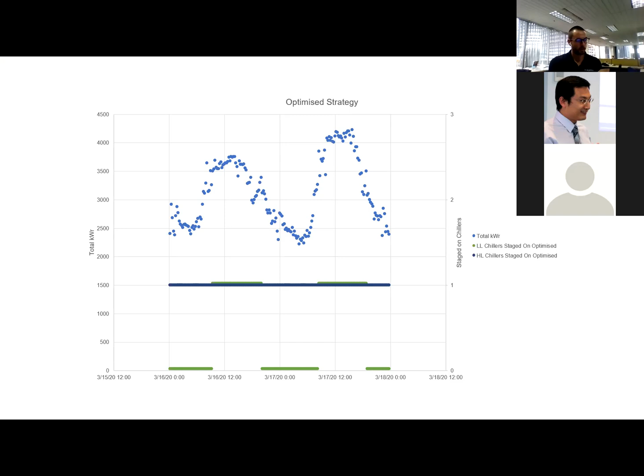The next recommendation that came out was the dynamic condenser water temperature algorithm, and this probably looks like gibberish seeing it, but there's a graph next which shows it pretty well. But really what we're trying to do here is, rather than going wet bulb plus X and having a constant approach, we're using a dynamic approach.